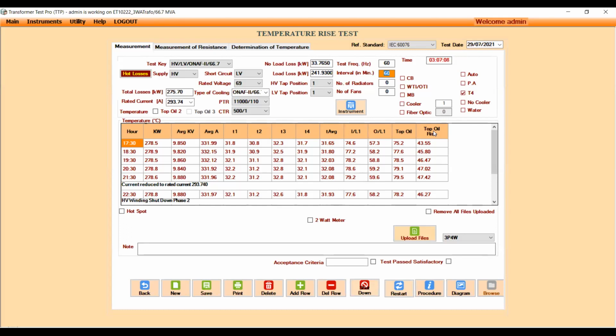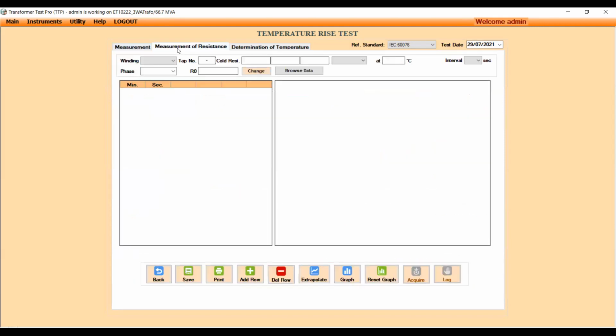Once this gets tabulated automatically every 60 minutes, 30 minutes, or whatever time you have set, the moment the temperature gets stabilized, the system asks you to reduce the current, and then asks you to shut down. Once you have shut it down, the next step is to go for measurement of the resistance of the winding.